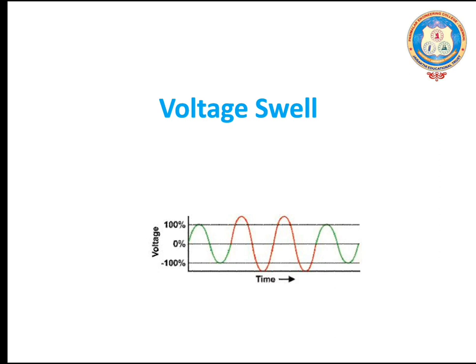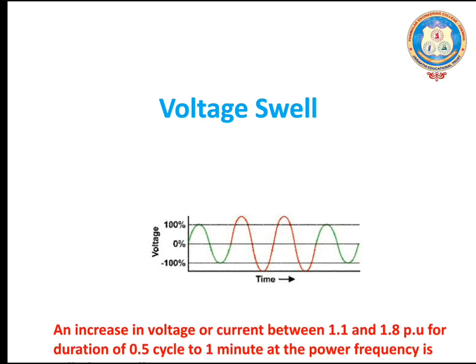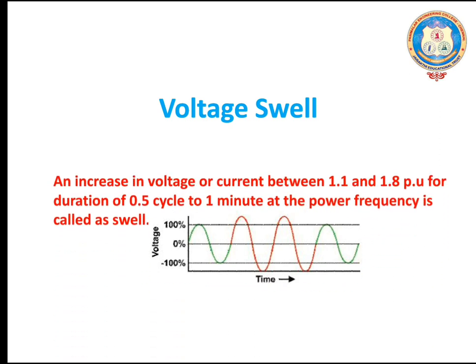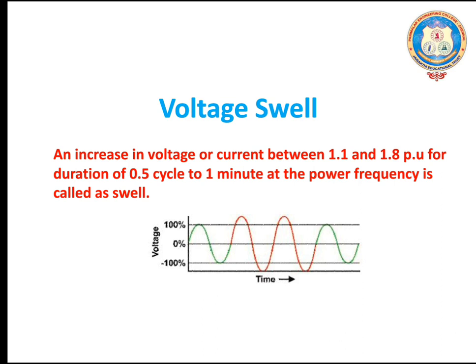Define voltage swell. Voltage swell is a short duration variation in which an increase in voltage or current occurs between 1.1 and 1.8 per unit, which occurs for a duration of 0.5 cycle to 1 minute at the power frequency.